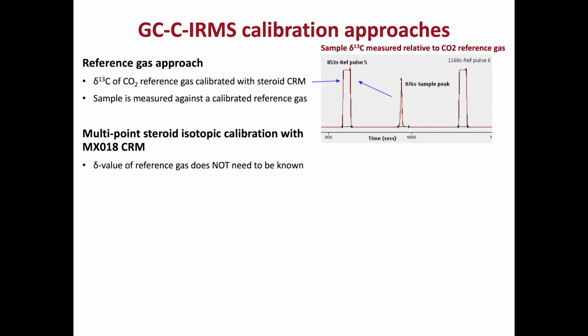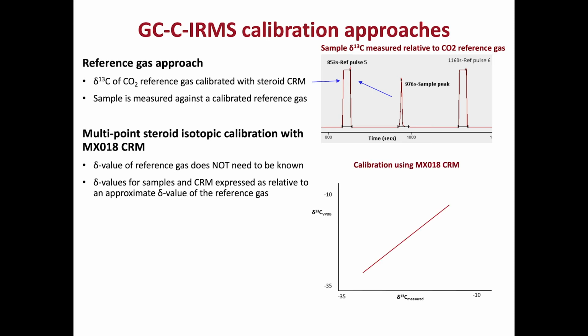The multi-point approach eliminates the need to know the delta value of the CO2 reference gas. However, setting an approximate delta value to the working gas is a good practice as it enables an analyst to perform a visual assessment of the instrument performance against the required acceptance criteria from the raw delta values. The new approach facilitates calibration of a range of delta values rather than a single point offered by the reference gas approach.